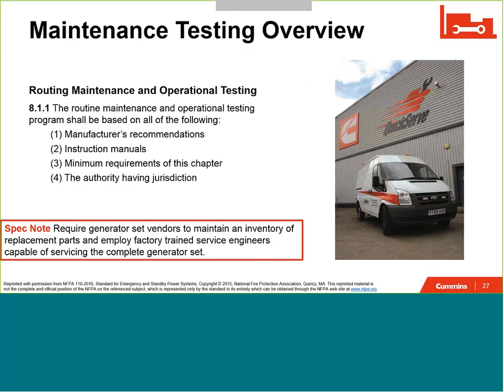It says the routine maintenance and operational testing program shall be based on all of the following. And I'd like to point out that the first two items called out by NFPA 110 are the manufacturer's recommendation, that's the product manufacturer's recommendation, and the instruction manuals provided by the generator or the component manufacturer. This is a key point because many times what we see are generator manufacturers have qualified and trained technicians that come on site and support the commissioning and installation of the product, and after that, if those technicians are not the ones servicing it, it may be owner technicians or others that may not be following the same maintenance testing requirements, which clearly does not meet the expectations of NFPA 110.